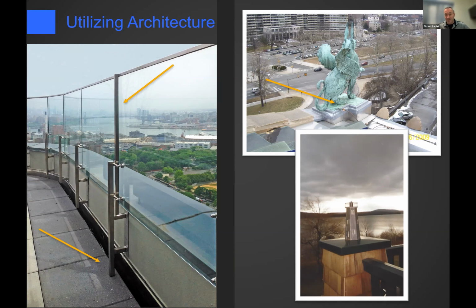We weren't going to put a lightning rod on top of that because that would ruin the art. But what we did do was just bond the giant bronze statue to the system. Now it's grounded. We've provided lightning protection. You can see the cabling down there in the bottom right of that picture. We provided a network of cabling and grounding all the way down through the structure. And now it's code compliant. And they don't have to see any lightning rods on the ears of that griffin or whatever the hell it was.